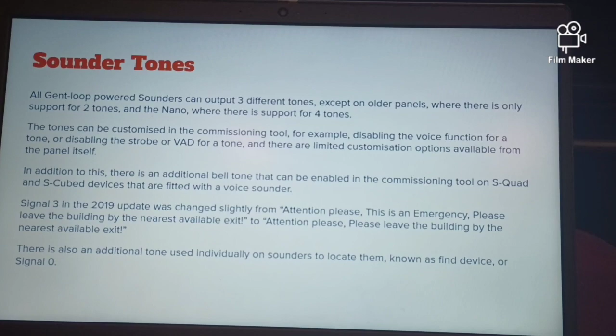Sounder tones. All Gent loop-powered sounders can output 3 different tones except on older panels, where there is only support for 2 tones, and the Nano where there is support for 4 tones. The tones can be customized in the commissioning tool, for example, disabling the voice function for the tone or disabling the strobe or VAD for a tone. There are limited customization options available from the panel itself. In addition to this, there is an additional bell tone that can be enabled in the commissioning tool on S-Quad and S-Cubed devices that are fitted with a voice sounder.